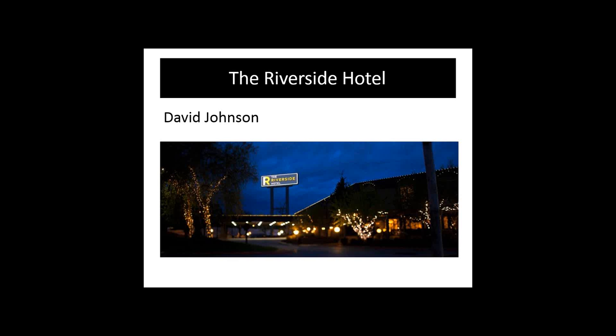But at the same time, we reconditioned all 34 rooftop units. In the common areas, we have 34 rooftop units. Some we've replaced, which is great, but a lot of them we just reconditioned, and we got the economizers cleaned up and working. I know those things are paying benefits to guest comfort as far as the airflow, and that has helped us a lot.